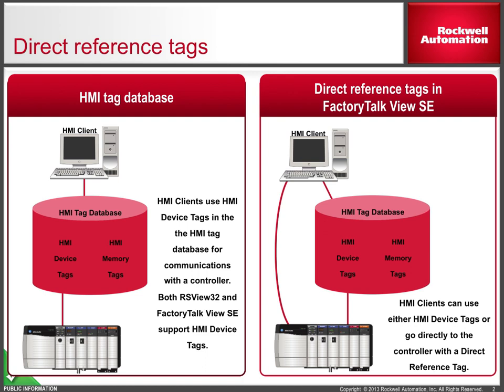As we talked about in previous videos, FactoryTalk View SE provides device and memory HMI tags just like RSView32 does. View SE also provides direct reference tags, which allow objects on the display to make a direct reference to a tag in the controller without going through the tag database.